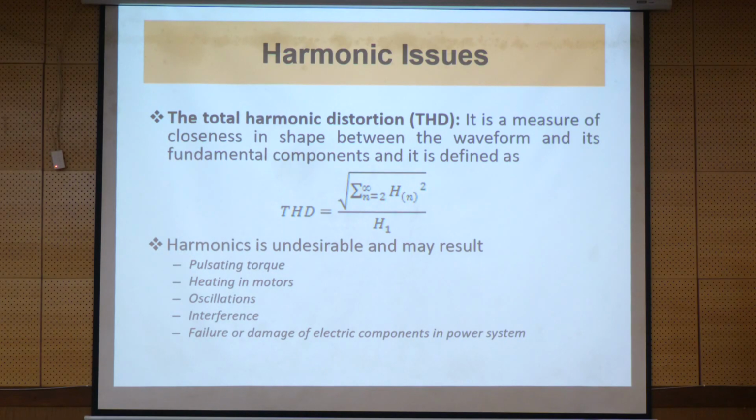Harmonics are an undesirable component in your system, and if they are present, these are the consequences: pulsating torque, heating in the motors, oscillations, interference, and failure or damage of electrical components in your power system. It has to be avoided. These are the things that we want to improve by using the converter, the multi-level inverter concept.